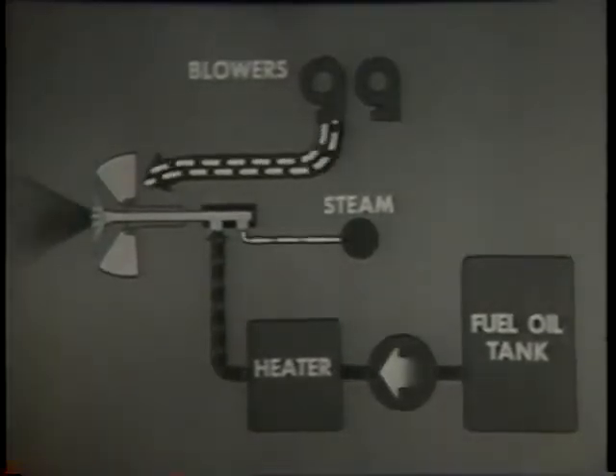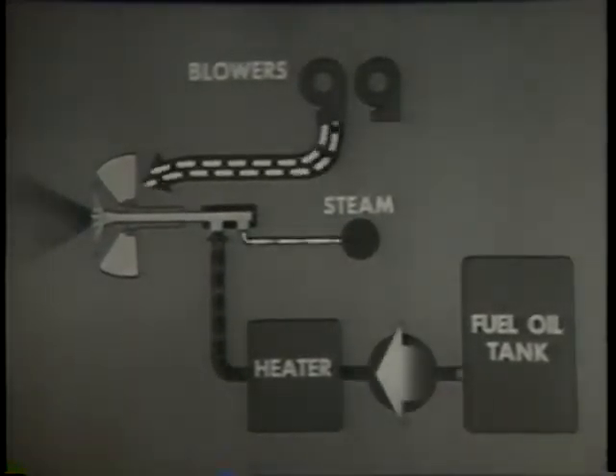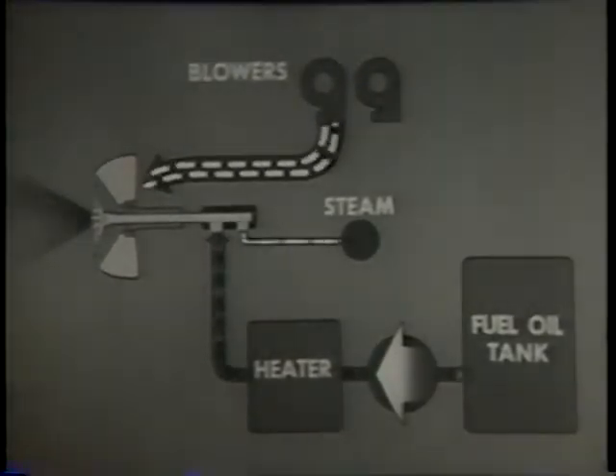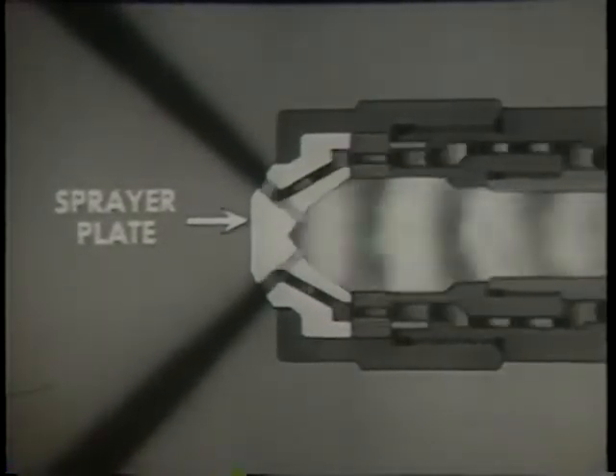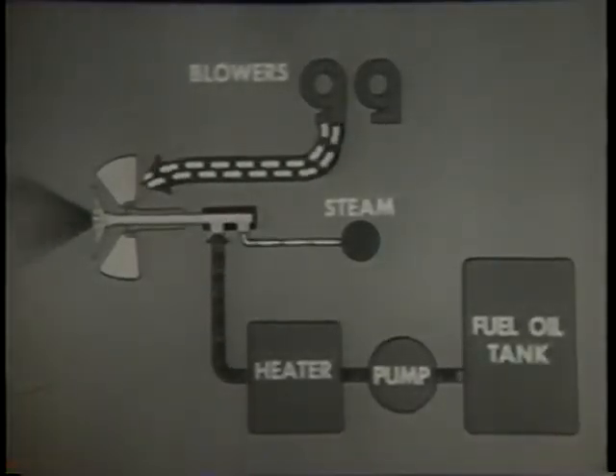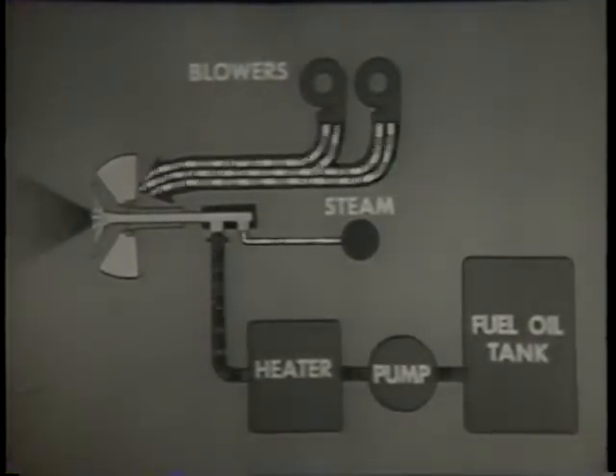Regulate oil pressure to control the quantity of oil. When you increase or decrease oil pressure, you must change the steam pressure correspondingly to get good atomization. You must also change the sprayer plate in the burner if the capacity of the plate is incorrect for the new firing rate. As with most burners, you adjust the speed of the blowers and the number in service to control the air supply.